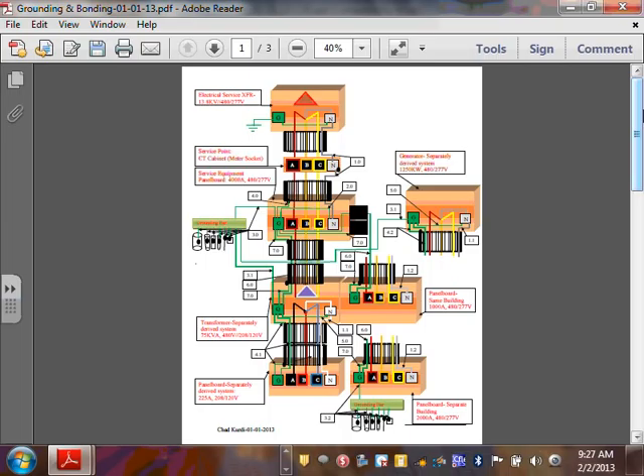The reason I picked these for you guys is that, remember, we're talking about grounding and bonding. Each one of them has special characteristics and rules for grounding and bonding. I didn't pick a transformer just because. This is your separately derived system. So everybody gets it: here's my feeder, transformer, through a panel, separately derived system. If you come to this side, I picked another panel that could be fed from a 2000 amp switchgear, switchboard, or a 4000 amp switchgear, or it could be a 60 amp panel fed from a 100 or 200 amp panel in your garage. So it goes wherever you want to go. So that's that sub panel. The only difference for this sub panel is that it's inside the same building.